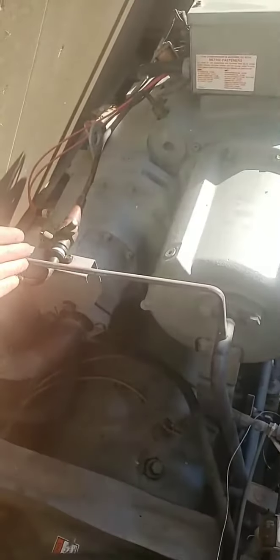So, your screw mechanism is on this side, and this whole side right here is all part of your motor. We can get a good shot of it this way and kind of see where it splits. So this is your screw, your actual compressor side of the system. This is your actual motor side. So you've got a 3-phase motor inside this cavity. This motor drives the screws through a series of gears right here.